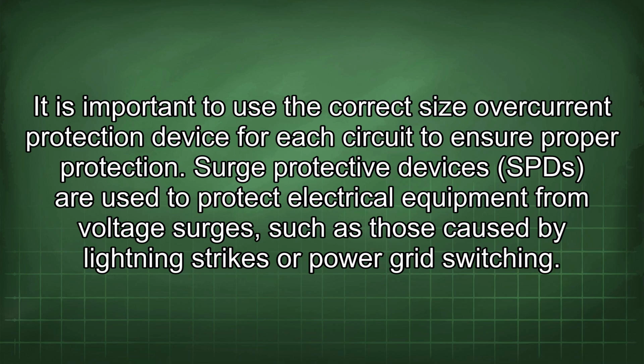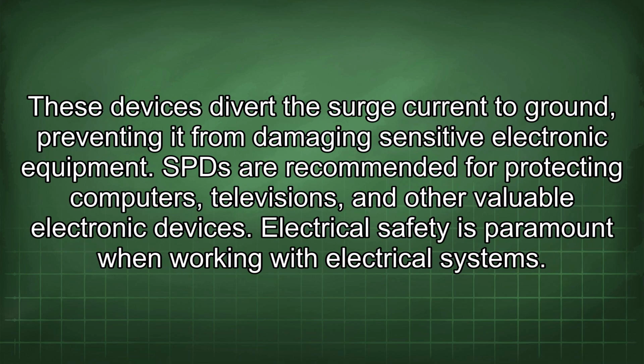protection. Surge protective devices (SPD) are used to protect electrical equipment from voltage surges, such as those caused by lightning strikes or power grid switching. These devices divert the surge current to ground, preventing it from damaging sensitive electronic equipment. SPDs are recommended for protecting computers, televisions, and other valuable electronic devices.